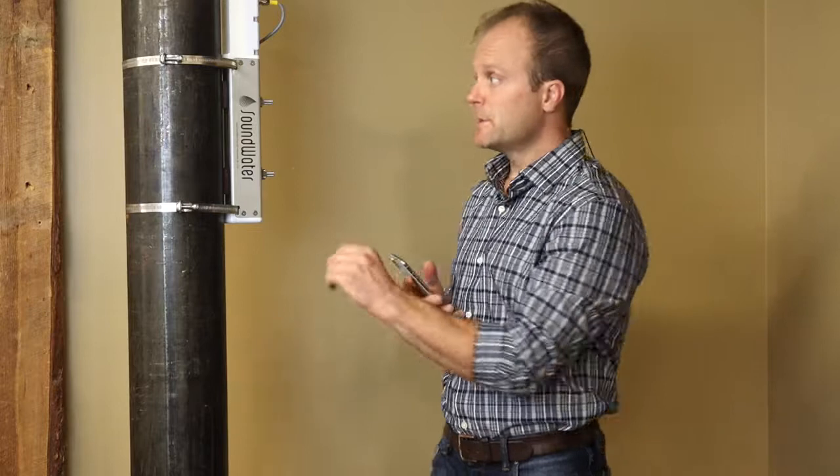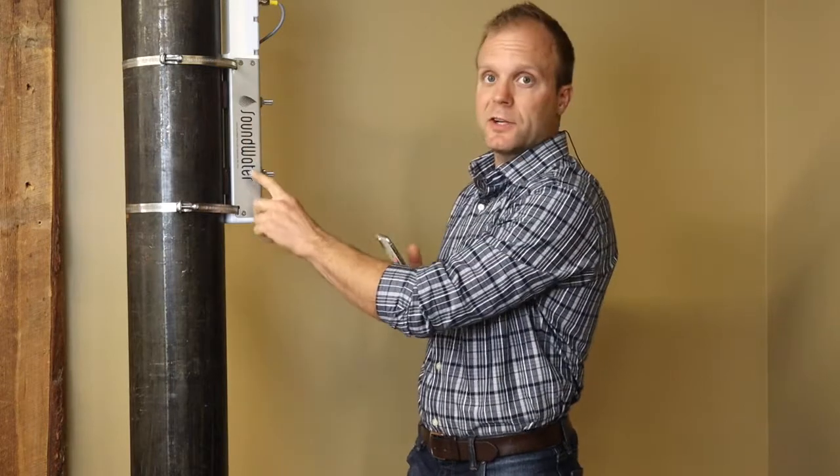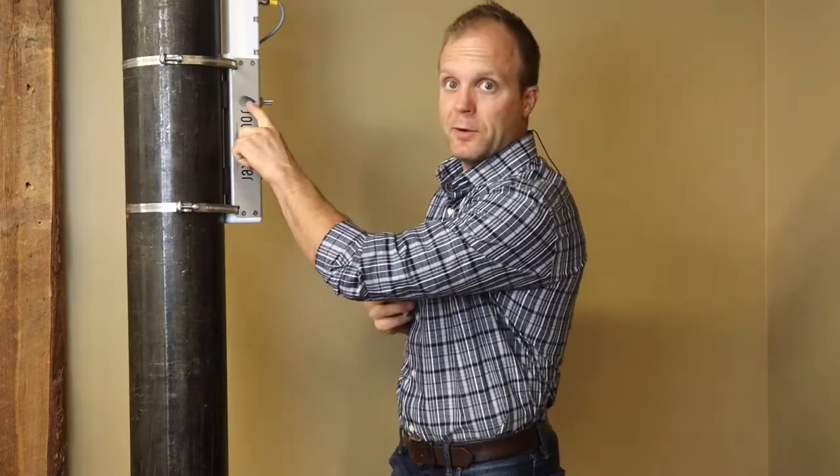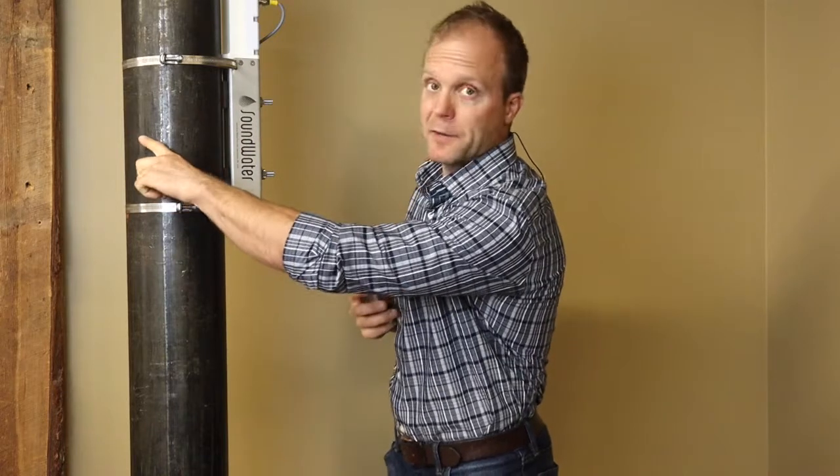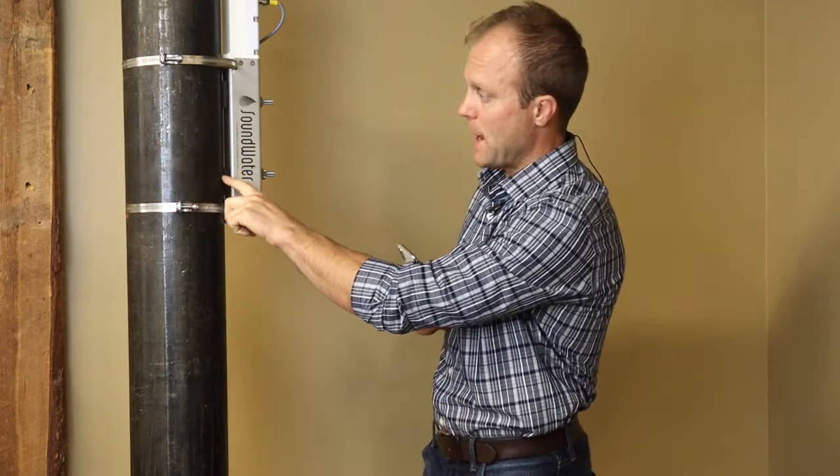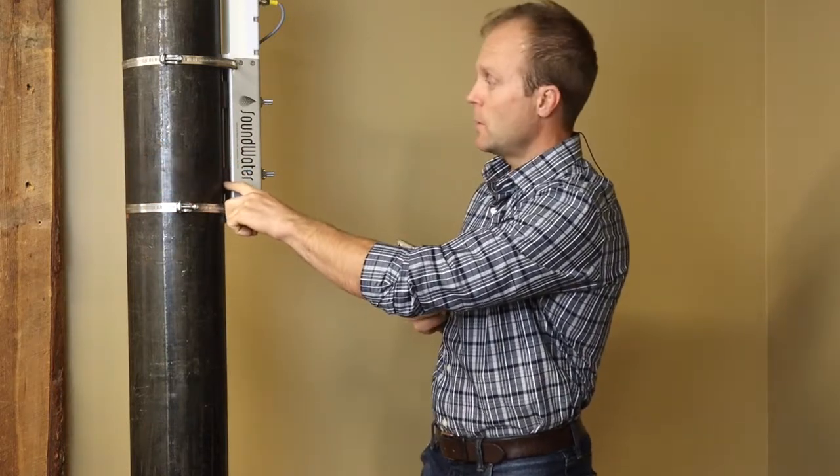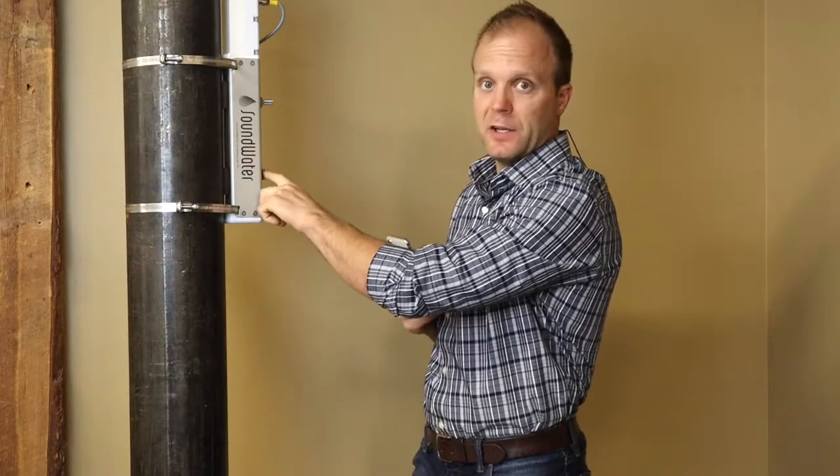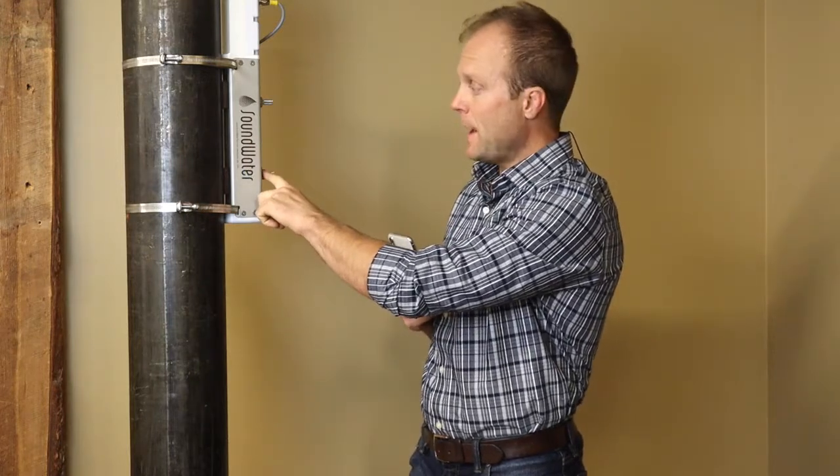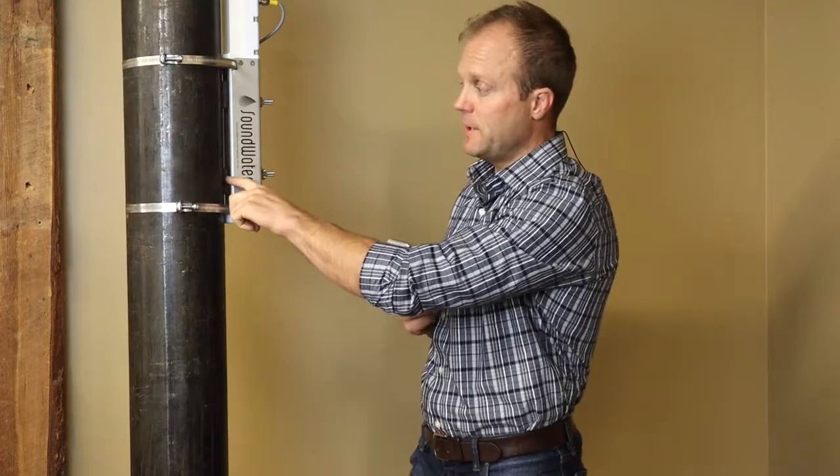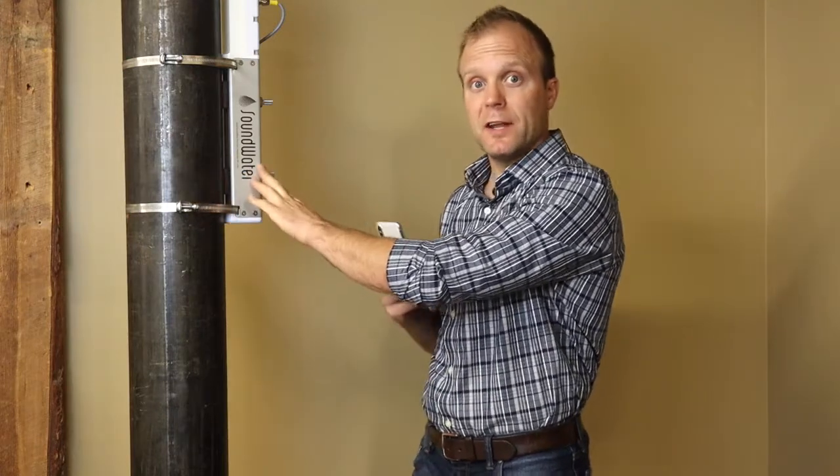And the reason for this is because there are two transducers here. One is transmitting ultrasound into the pipe. It bounces off the back side and the ultrasound comes back to the surface right here. So we need to position the second transducer at the right spot where the ultrasound is hitting the top of the pipe so it can receive it and make a flow measurement.